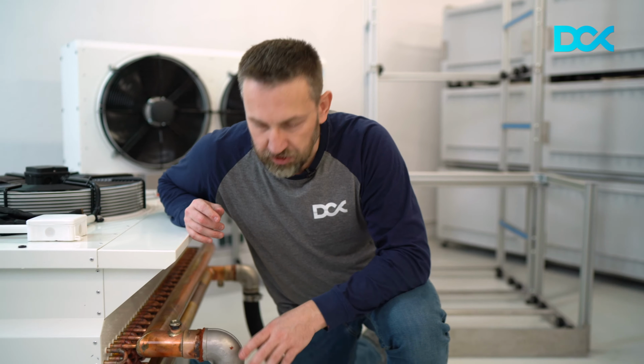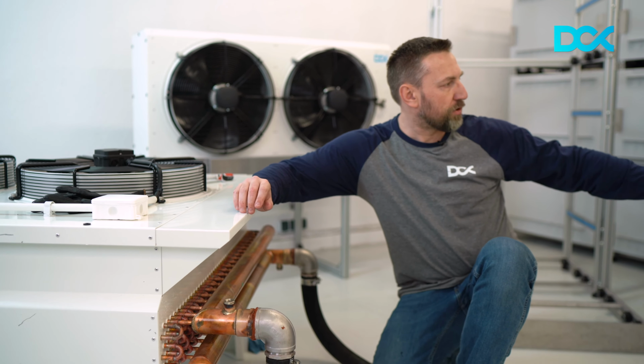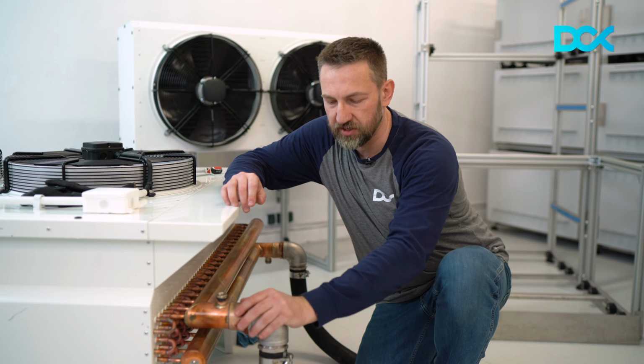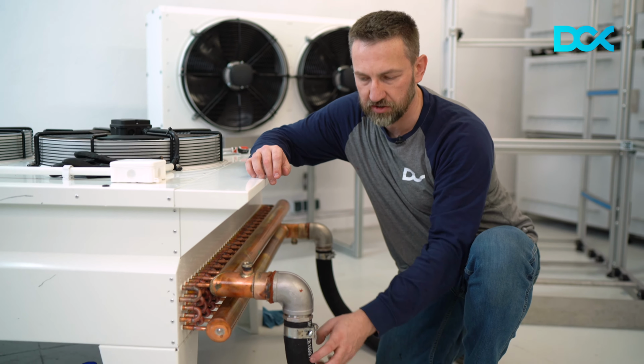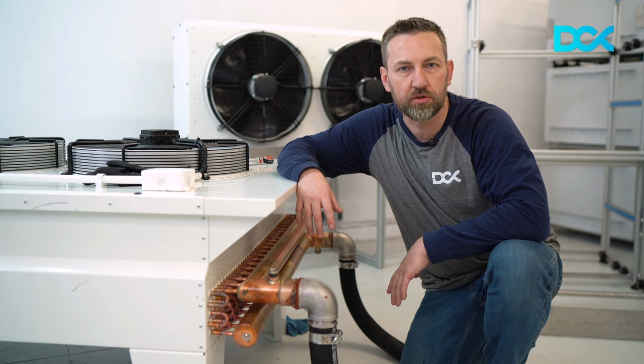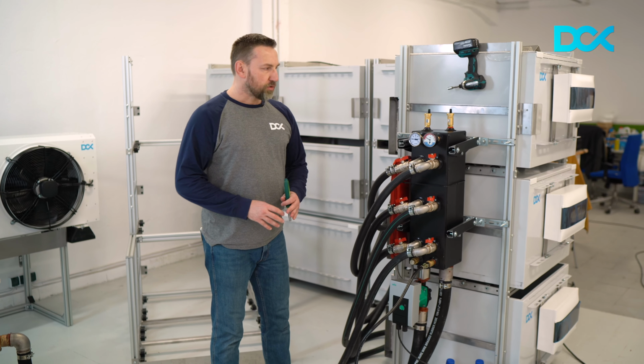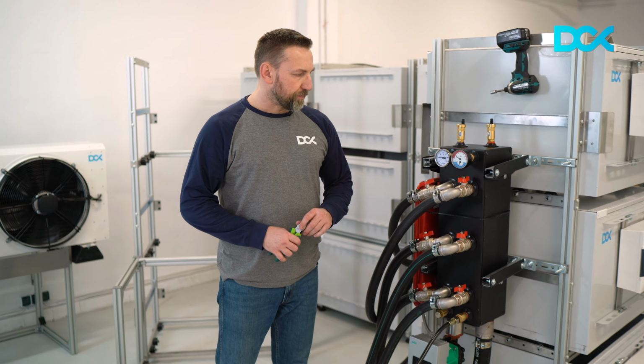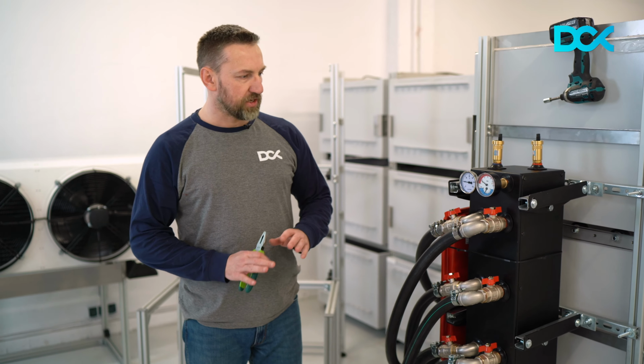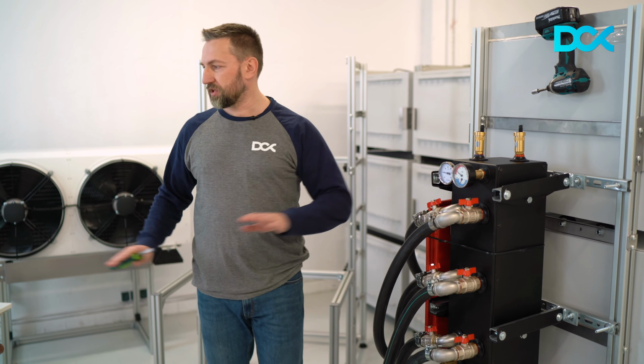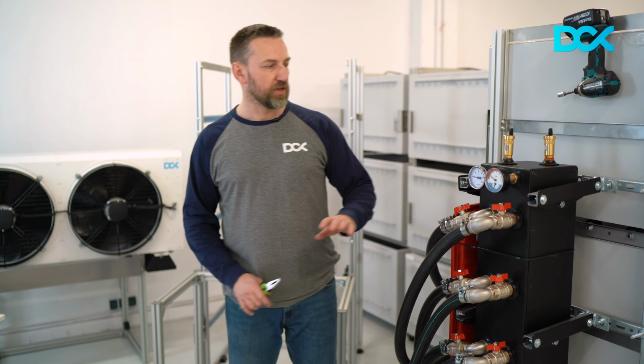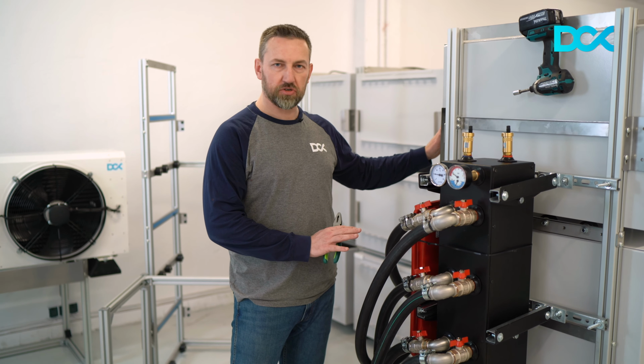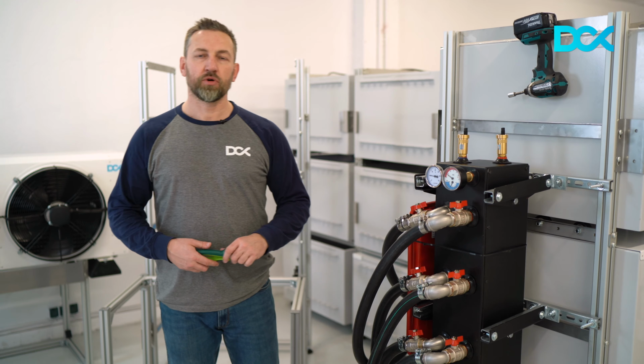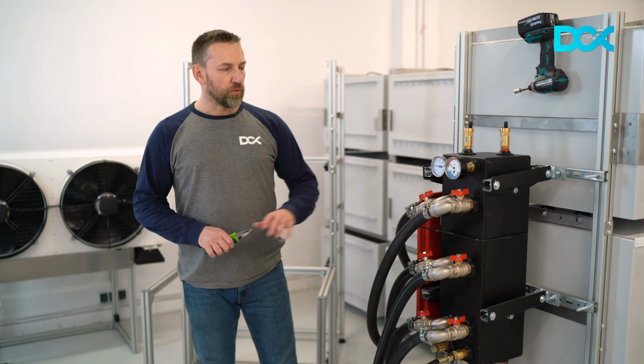You know, guys, that's it, more or less. We have the system pressurized up to 2 bars. We connected both black box and pumping system with the hose fittings on the dry cooler system. And now what we need to do is to start the dry cooler. Okay, so one more thing in regards to the pressurization of the system and basically air release. It is most important to be 100% sure that we don't have any air within the system. Then the dry cooler works and all the heat exchangers, brazed plate heat exchangers on the enclosures, work at full capacity. Now we just started the operation.